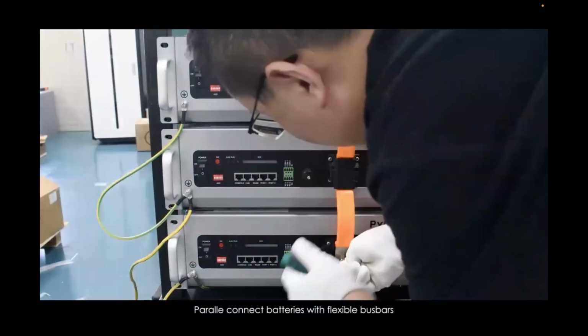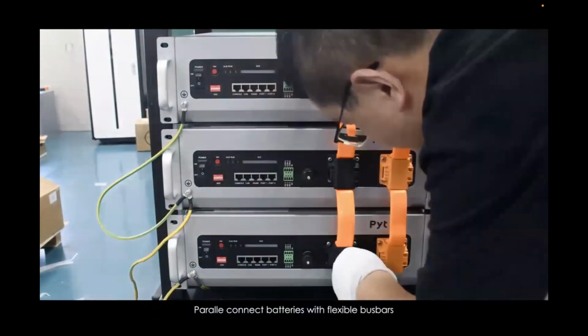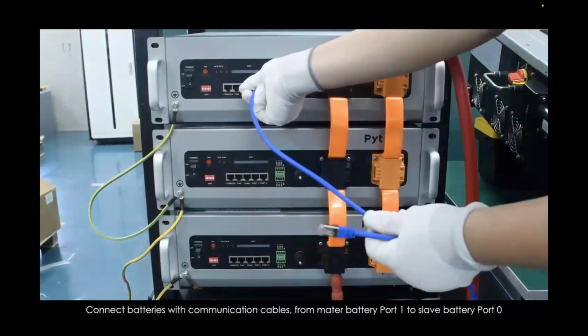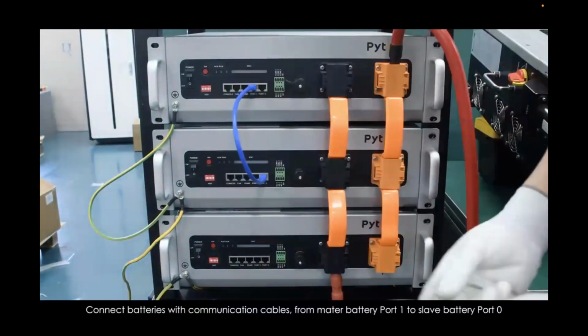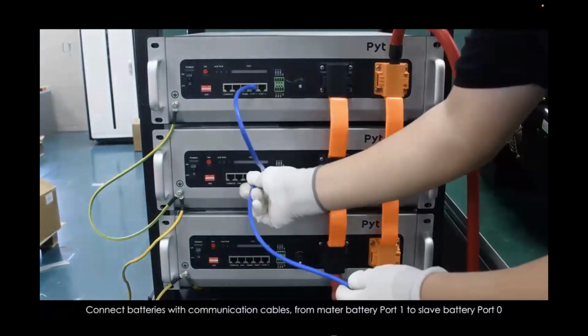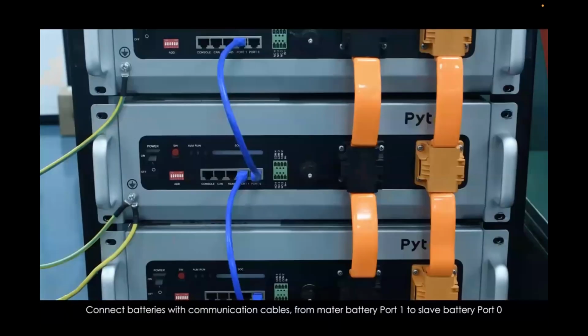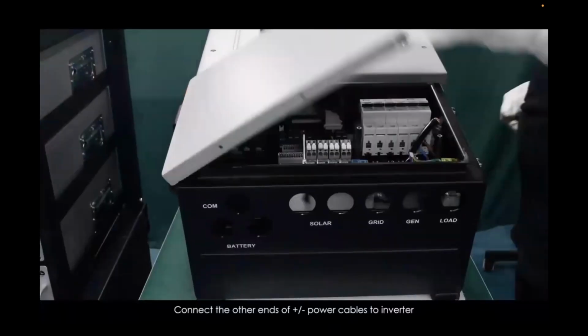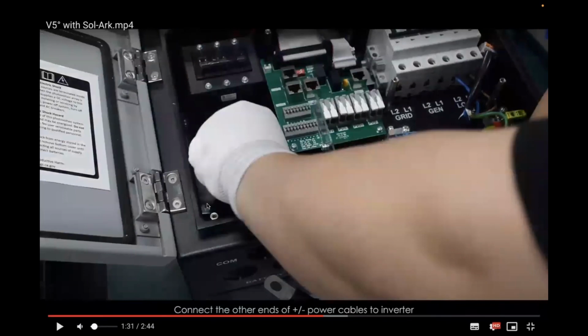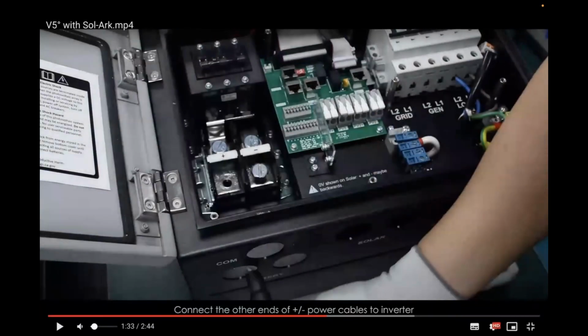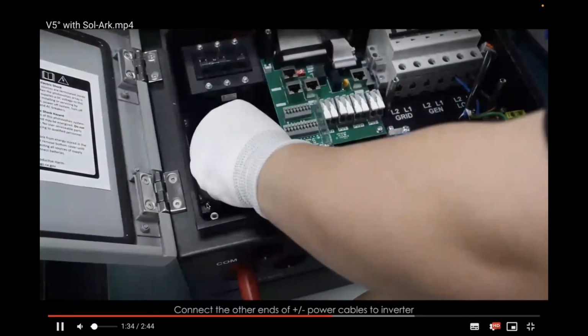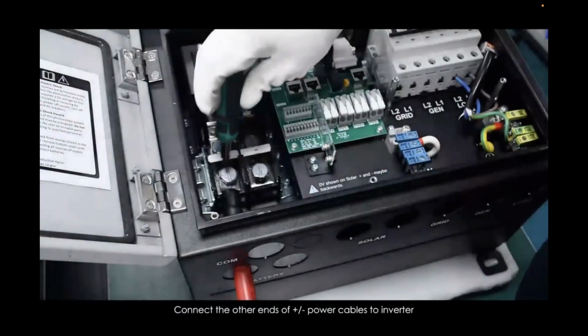Then we're running our positive leads at the top and negative leads at the bottom, cycling the system correctly and taking that to the inverter. This is also a demonstration of how the communication cables are hooked up so the BMSs are communicating with one another, and we're running and connecting our battery cables directly into the Sol-Ark inverter safely.